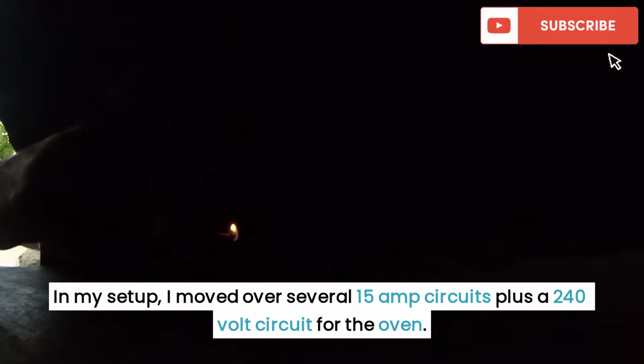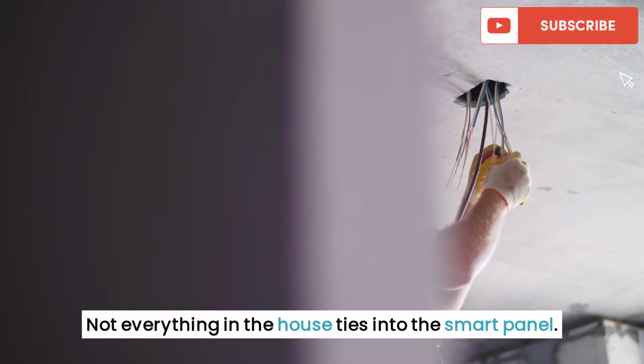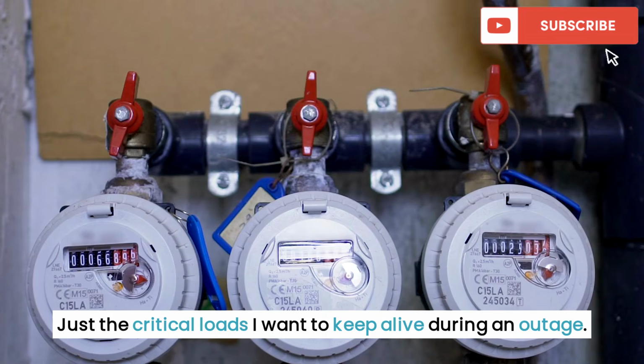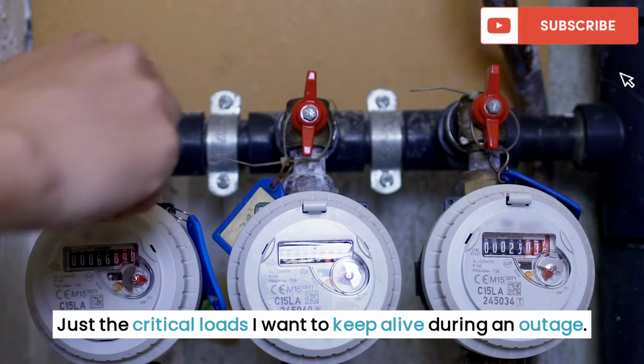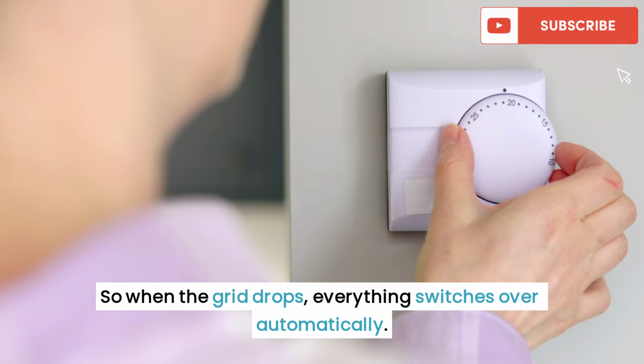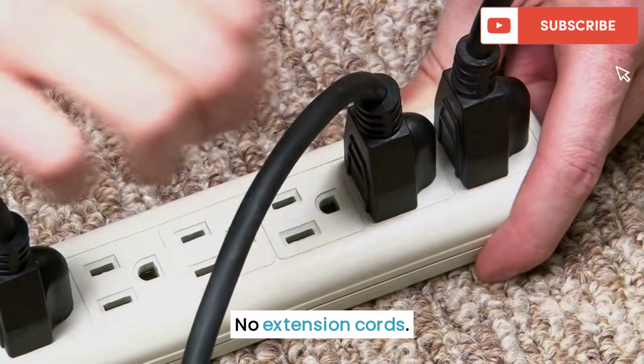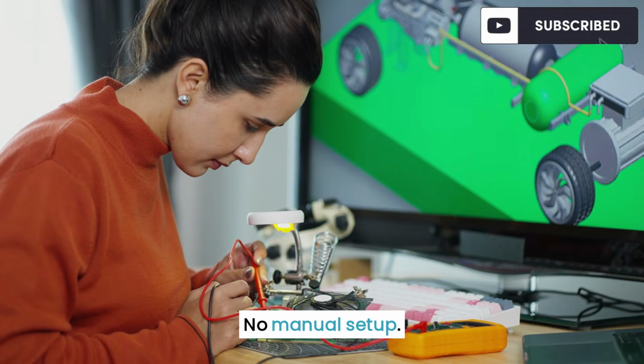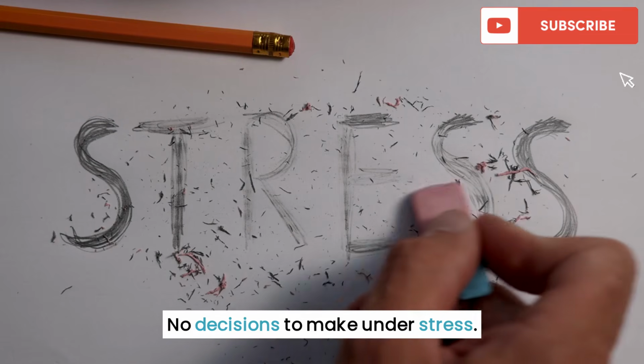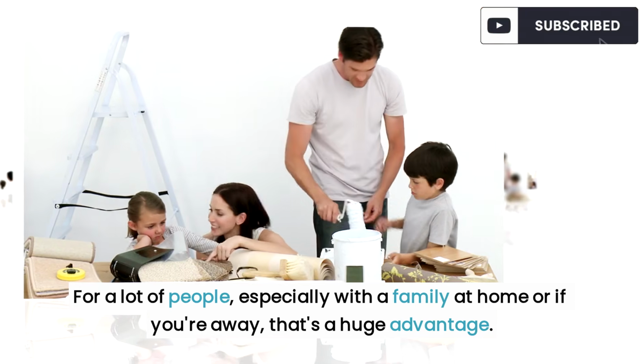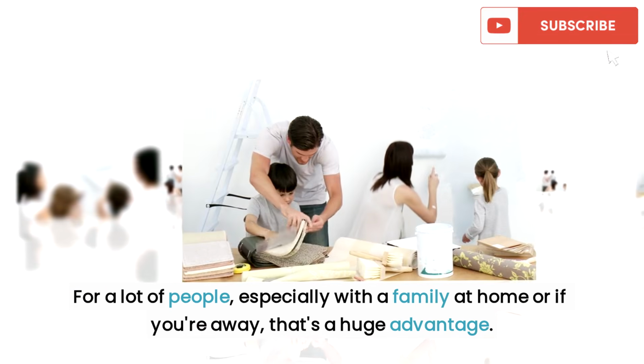In my setup, I moved over several 15-amp circuits, plus a 240-volt circuit for the oven. Not everything in the house ties into the smart panel, just the critical loads I want to keep alive during an outage. So when the grid drops, everything switches over automatically. No extension cords, no manual setup, no decisions to make under stress. For a lot of people, especially with a family at home or if you're away, that's a huge advantage.